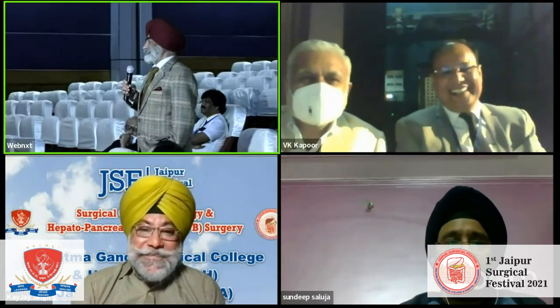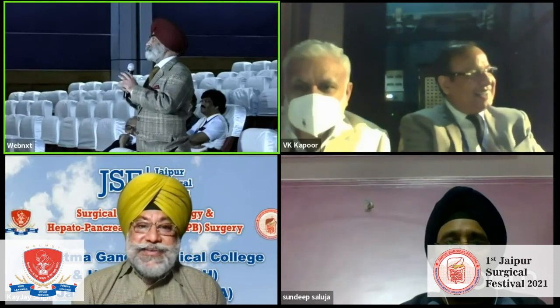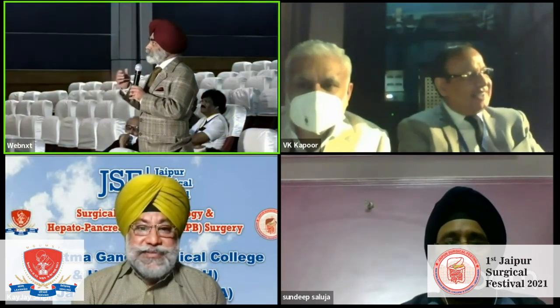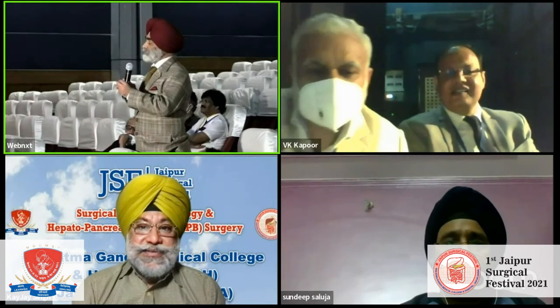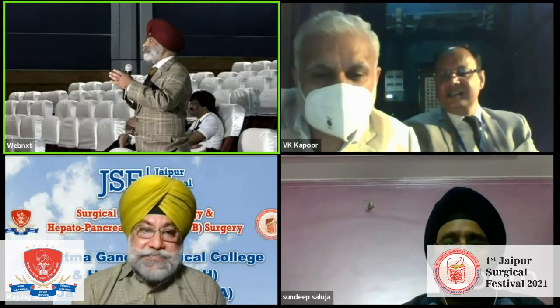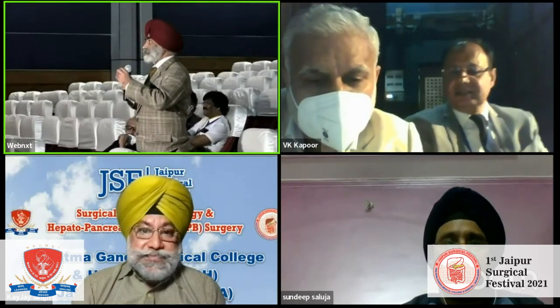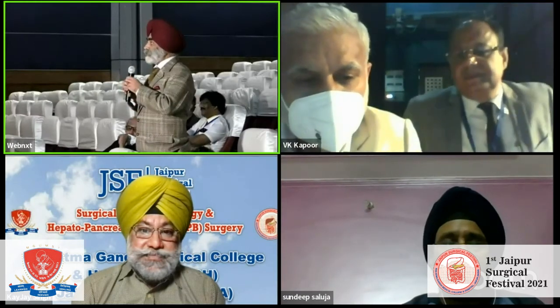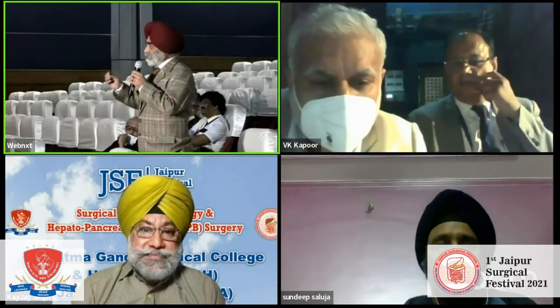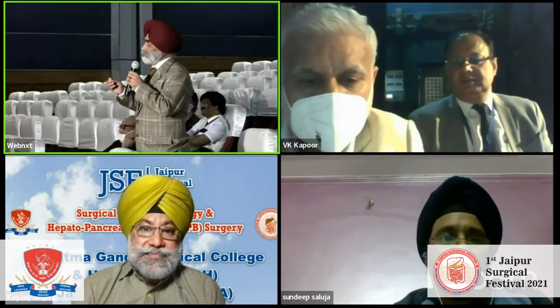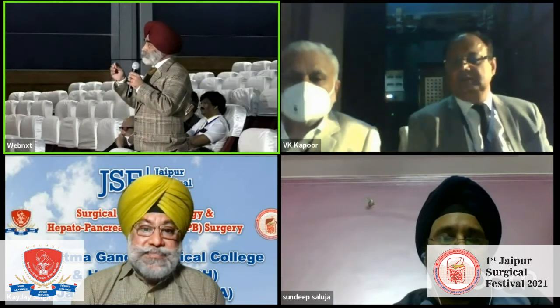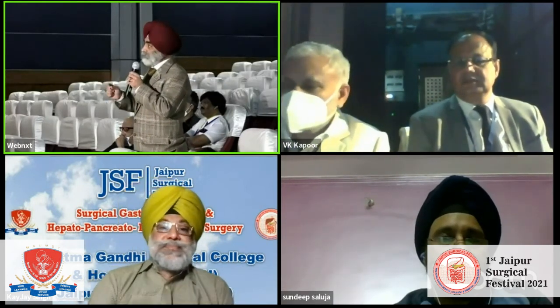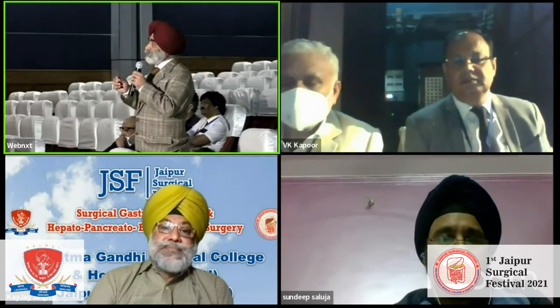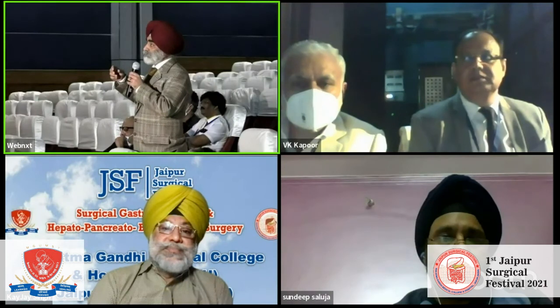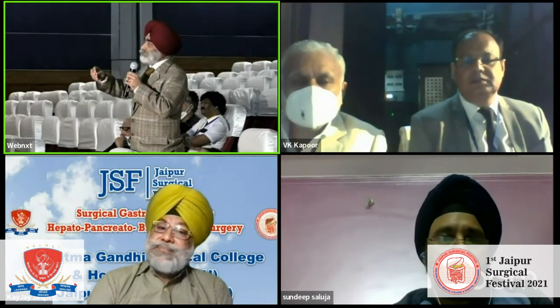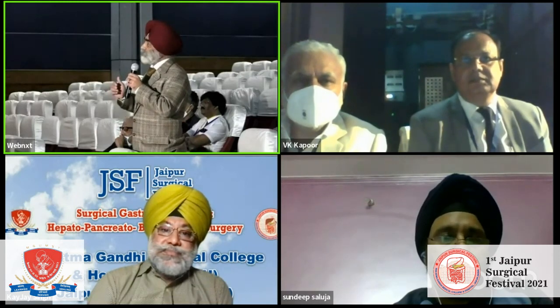Okay. This is a very important aspect which has often been neglected, and I suggest that it be included in the curriculum. We should encourage classes for this. You can have a fault at multiple levels: the light going off when you are doing the artery, or a bleeder from the use of cautery. As you very rightly pointed out, a common point where a young surgeon can make a disastrous mistake is using the cautery when the entire metal part is not seen and something is being injured. The instrument should only be introduced after the lead has been put on, because if somebody is putting the lead on from behind, it can accidentally get pushed inside, and if the cautery is activated, it can cause serious injuries.